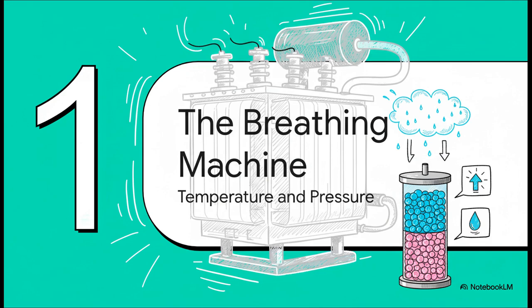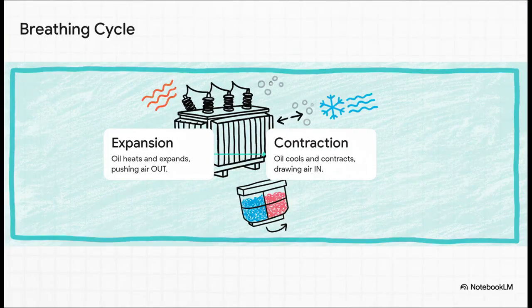The breathing machine. Now, I know that sounds weird, but yeah, transformers have to breathe. And it's all driven by temperature, pressure, and the huge amount of oil sloshing around inside them. Here's how that cycle actually works. When a transformer's really putting in the work, its insulating oil gets super hot. And what happens when things get hot? They expand. That expansion pushes air out of the transformer. Then, when things cool down, the oil contracts, and that creates a vacuum, sucking the outside air right back in. And that's it. That's the breath we're talking about.